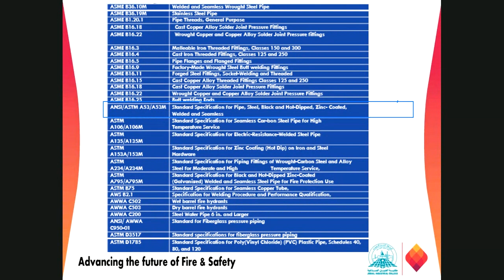This is the standard specification for pipe, steel, black and hot-dipped, zinc-coated, welded and seamless. It is the most common we are using in our fire protection applications. After that we have ASTM A106, which is the second most common, and we are using it for high temperature services, mostly for the deluge valves installed in the process industries. And AWWA C502, which is for the wet barrel fire hydrant, and the American Water Works Association standard for the dry barrel fire hydrants.